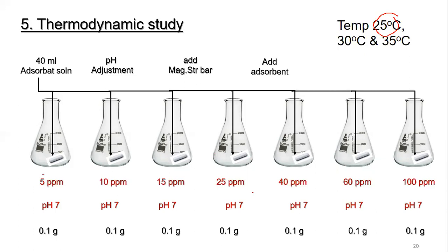But if there is any difference in the reading, for example the magnetic stirrer and heating plate shows that the temperature is 25 degrees, but you find out by using a manual thermometer inside the flask that it is, let's suppose, 22 degrees centigrade, then what you have to do is adjust it accordingly, and you increase it a little bit. And if you are sure that what's showing on the thermometer scale is accurate, then there is no problem.